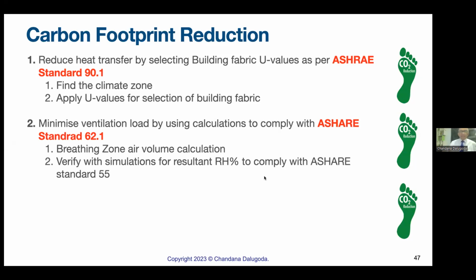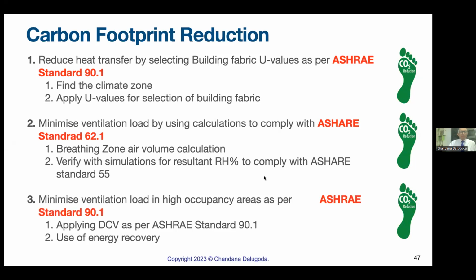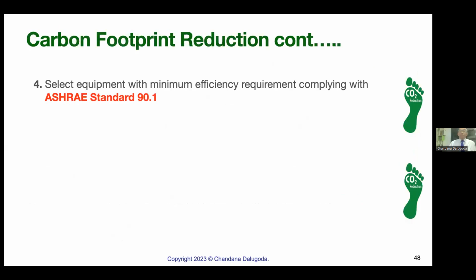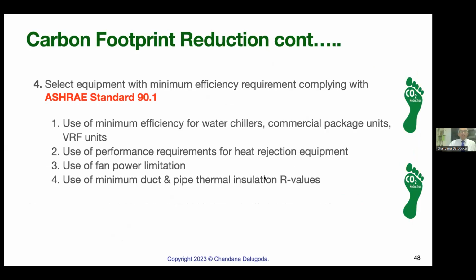ASHRAE standard has an upper limit. 60 RH is the upper limit of air conditioned space relative humidity. So we can see in the simulation what is the predicted value. If it is exceeding 60, if it becomes 65, 70, we'll have to take measures. Minimize ventilation loads in higher occupancy buildings. We'll have to use demand control ventilation. Select equipment with minimum efficiency. Again, ASHRAE standard 90.1 we'll have to use.